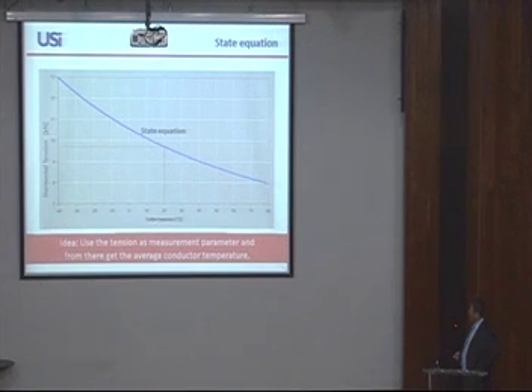I said to you that the temperature and the tension are correlated to each other. So the idea was, if I measure the tension and I know this curve, I have the information about the temperature of a conductor. And if you remember the second slide, you also know the sag, and from that you have the clearance information from the line. So measuring the tension is the same thing designers do. We follow the same path. We measure this value and go to temperature and go to sag.